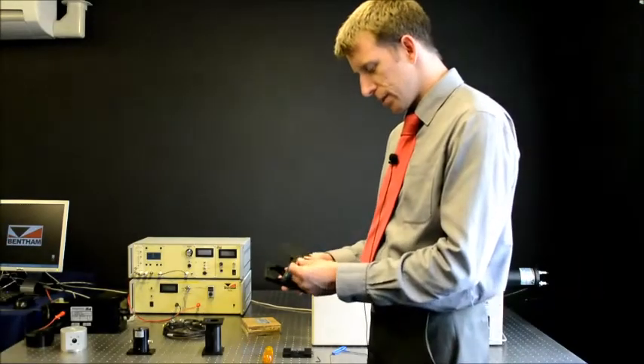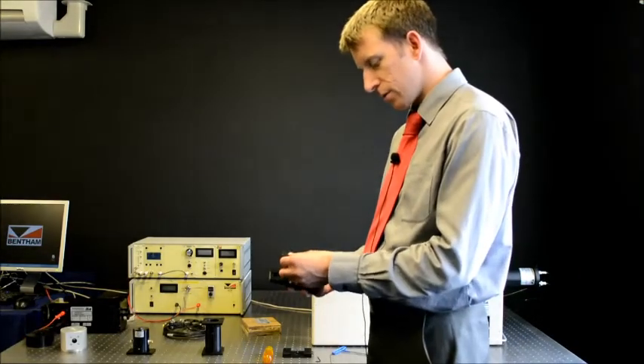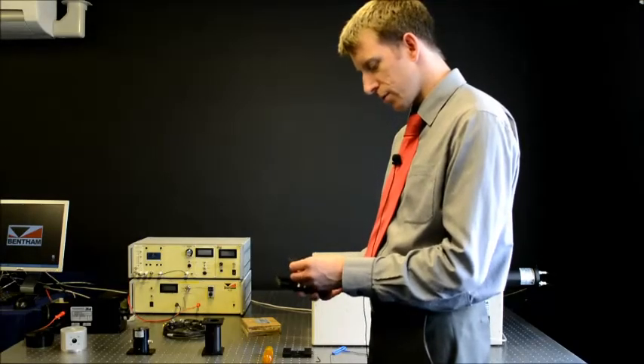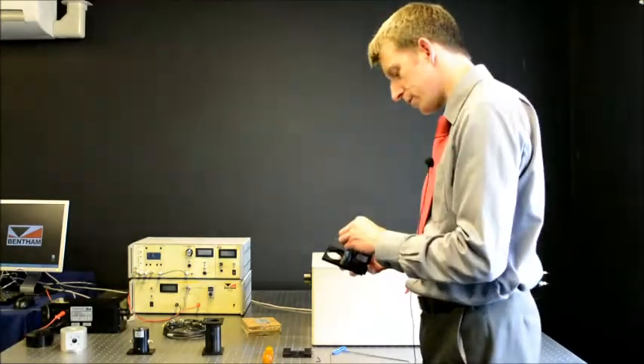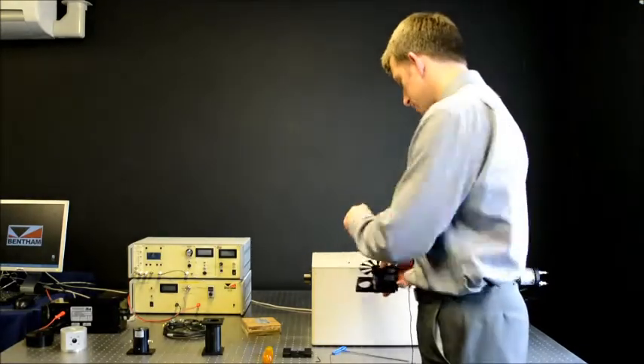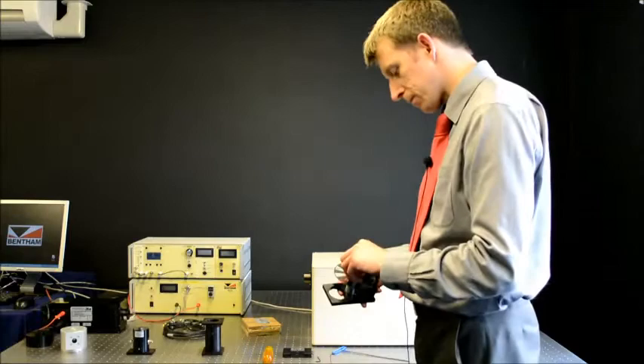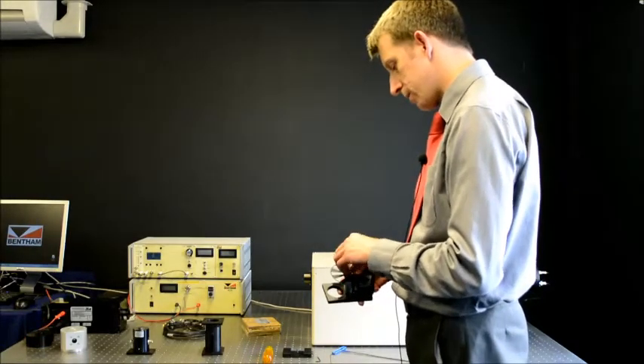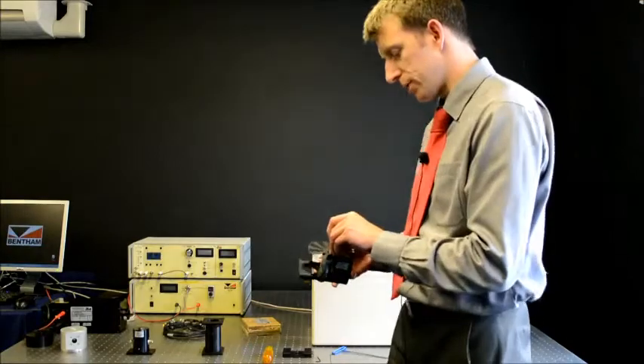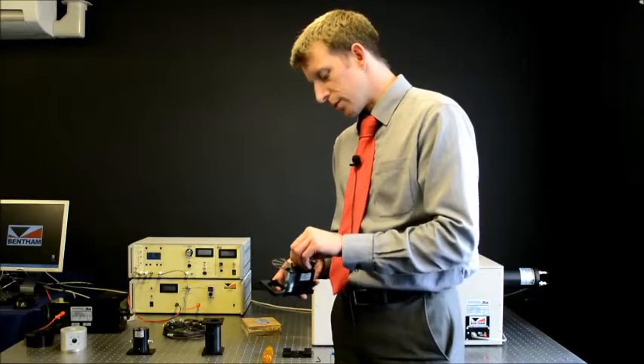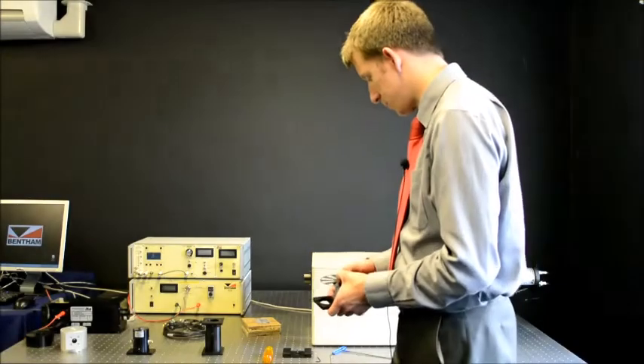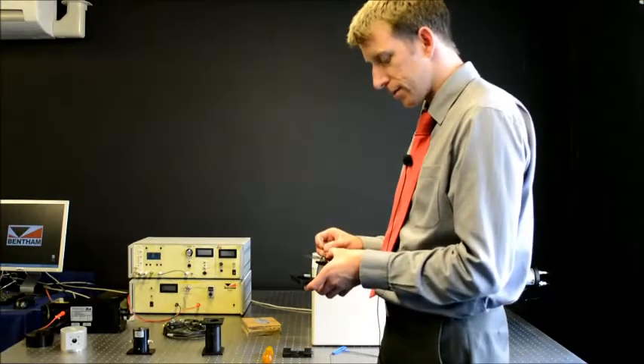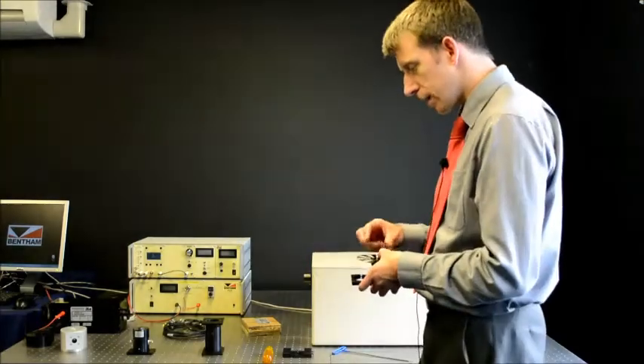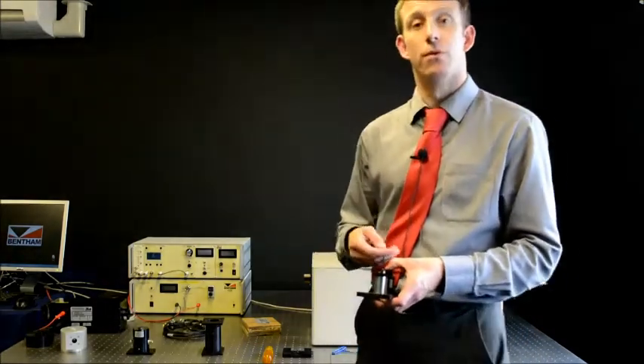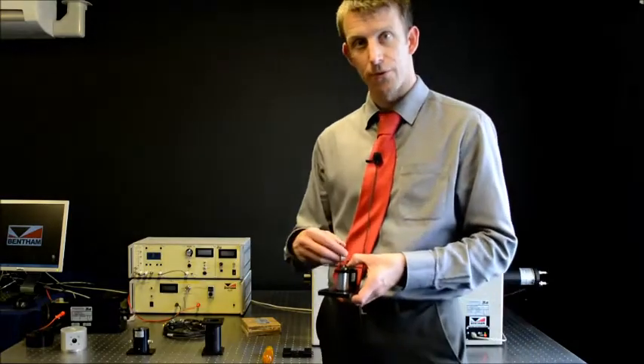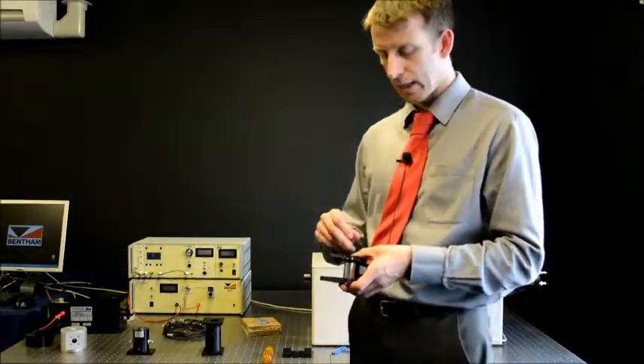The 10-slot blade should be positioned on the shaft of the 218 optical chopper, and the 3 retaining screws attached to hold the blade in place. We will then proceed, having firmly secured this, to attach this entire mount to the calcium fluoride based input optic. The calcium fluoride lens system is used for the reason that calcium fluoride transmits throughout the region, as opposed to, for example, glass or quartz.